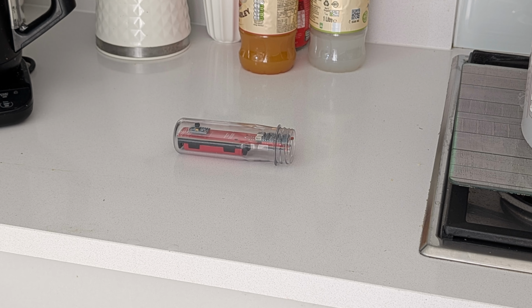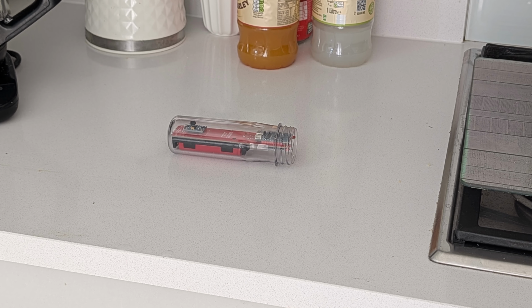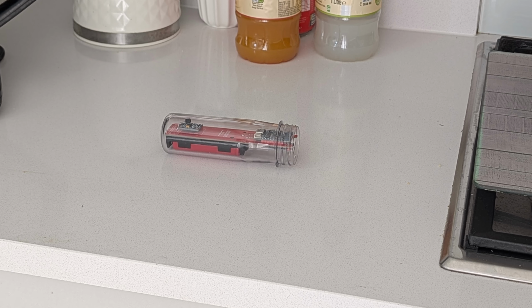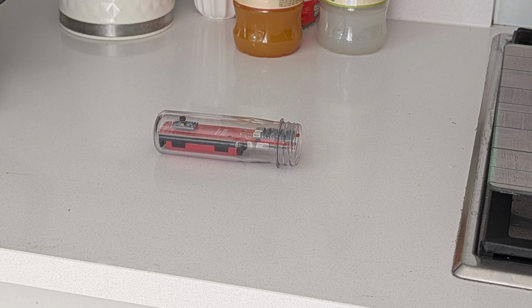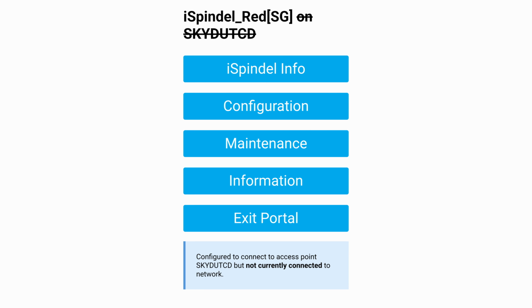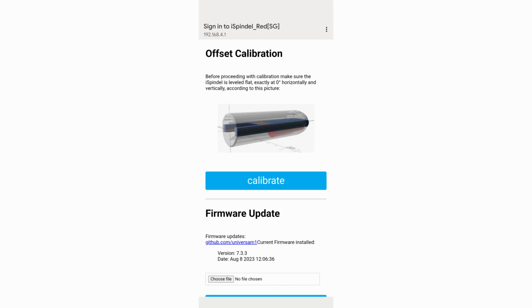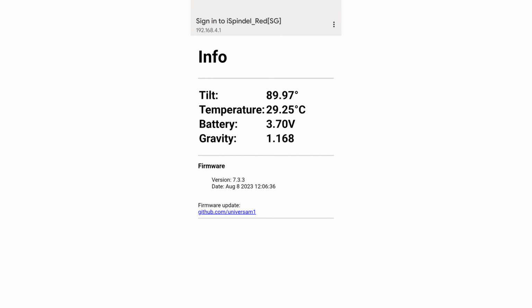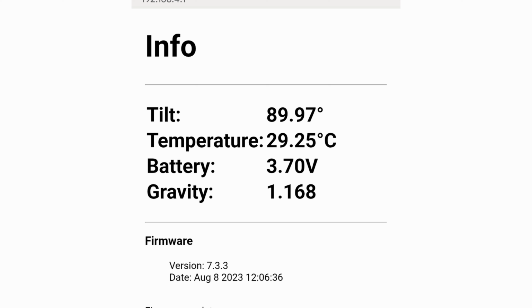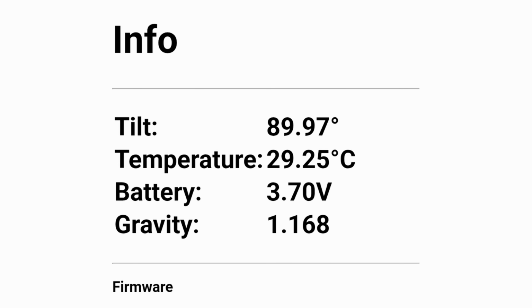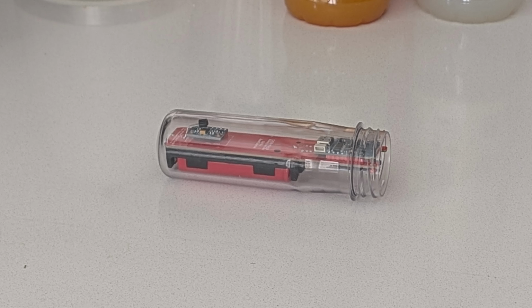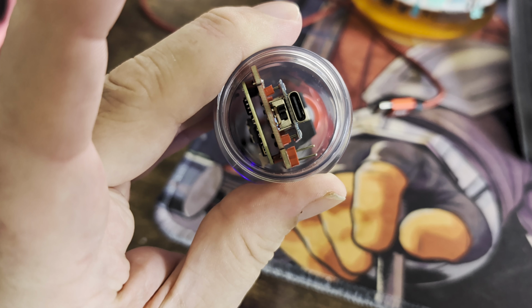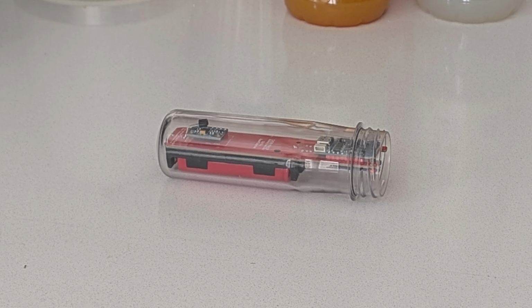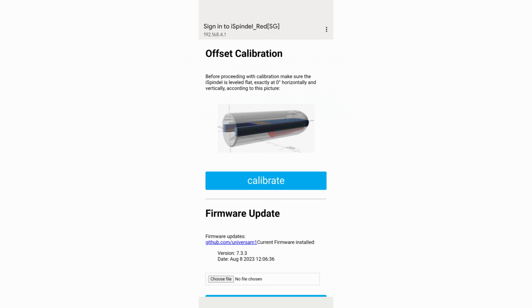For the horizontal configuration or offset calibration, we're going to first place the iSpindel on a good flat surface. Now it will rock for a moment and we need to wait for it to settle down and stop, and then go into the configuration menu, select maintenance, and then select calibrate for the offset calibration. Now this will only take a few seconds and the blue light will turn solid blue for a moment and then return to flashing once it's complete. If we now check on info, the tilt should show 89.9 degrees. Calibration is complete. Now, if it's giving any other reading, we need to make sure the surface is completely flat and the circuit board is firmly fixed inside the tube, and place it on the surface again and take another calibration reading.